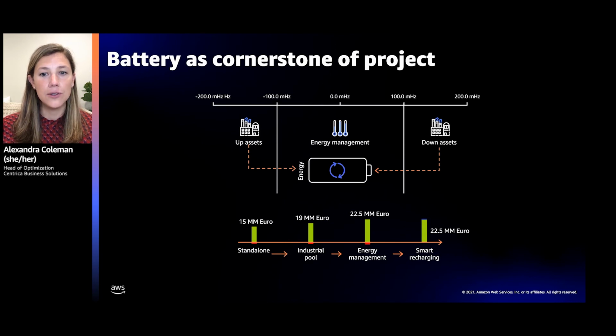As the compressor goes from 100 to 0% over 10 minutes, the battery will slow its discharge to match the ramping of the compressor. Once the compressor shuts down completely after 10 minutes, the battery can stop discharging and remain at its steady state of charge. Once the grid event is over, the compressor can start back up and the battery can potentially begin to charge again. You can see on this graphic, the up and down assets on the ends are the compressor shutting down and turning on, and the battery is helping to react quickly to the grid event.